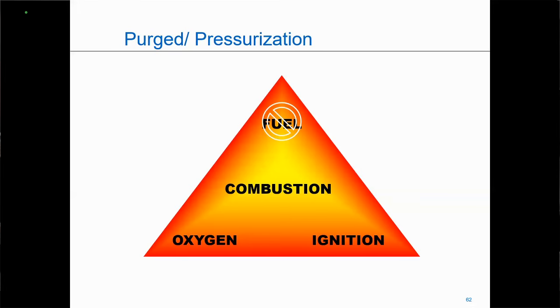An example would be June of last year, I got a call for an explosion-proof enclosure. The person said, I need a NEMA 7 explosion-proof enclosure. I need it to be 48 inches by 48 inches by 24 inches deep. Good luck, because one of those is this. So that's a perfect example for the purged and pressurized application. If one of those enclosures did exist, it would probably be close to 2,000 pounds, just to give you an example, and that's if it was made of copper-free aluminum. So in those types of applications, or some of these different areas, we're going to have equipment that is purged.